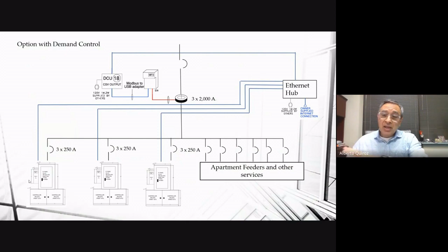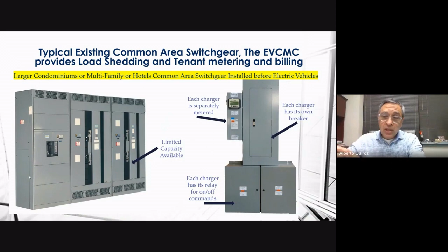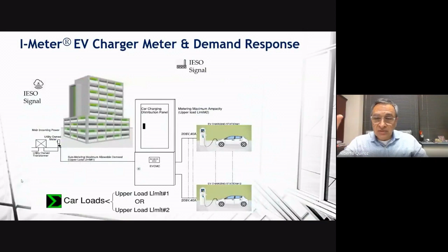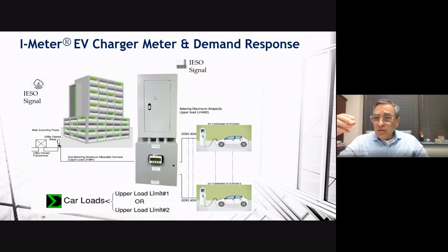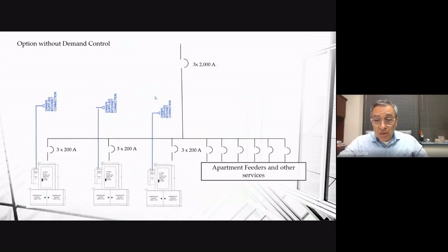Every building has a main switch gear at the entrance. The easiest way to install is looking at what's available in that switchboard to add an EVCMC, or two of them, or to add the meter in case capacity is going to be exceeded. You can add one, two, or three, and add more panels with time. You may do it independently, and over time you can add communication between those panels to make them work all together as if it were one.